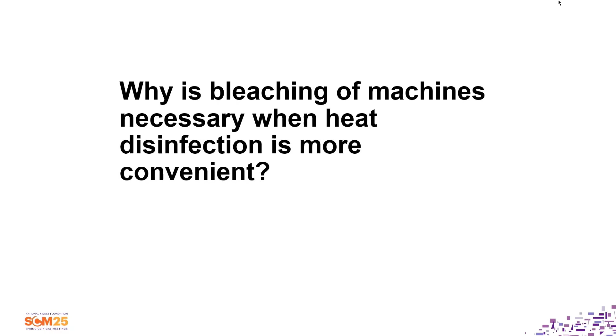And that's why, when I hate bringing up surveyors, because if it's being recorded and they listen to it. Anyway, so when surveyors come into my facility and say, show me your bleach log, I say, why? Because you're disinfecting. I said, no, we're not disinfecting. We use heat as a disinfection. And the reason why you check the log for your disinfection is to denote that you do not sample for cultures of bacteria immediately following disinfection. If you're heat disinfecting your machine every night, is there going to be a lag time between disinfection and sampling? No, there isn't. Your proof is you're heat disinfecting every night. Why does it need to be cultured? That we just included with our monthly.